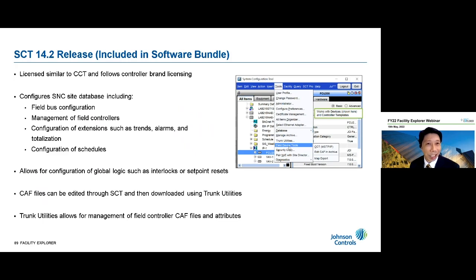We have the SCT and CCT to work with SNC. The SCT handles supervisory logic and configuration. You can edit the supervisory logic there to create points and manage the field controller at the management level, set schedules, trends, alarms, and totalization for the site.